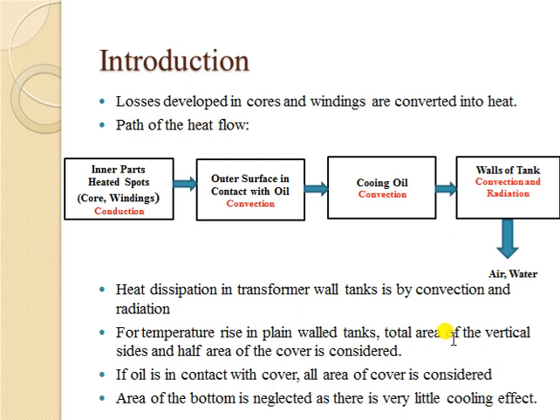Through convection again, heat reaches the walls of the tank, and finally through convection as well as radiation, heat is exchanged with the outermost medium — which may be air, water, or anything. Heat dissipation at transformer tank walls is by convection and radiation. For temperature rise in plane wall tanks, the total area of vertical sides plus half of the cover is considered.